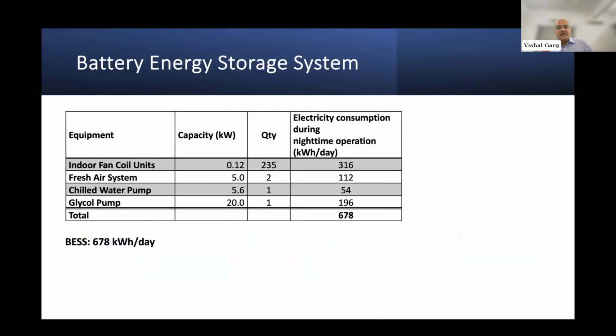And now we are trying to understand how much nighttime load will be there from running the pumps, the indoor fan coil units and the fresh air system. And we are designing a battery which will store this energy also from the energy generated in the daytime, so that the nighttime air conditioning load is 100% stored during the daytime using renewables.